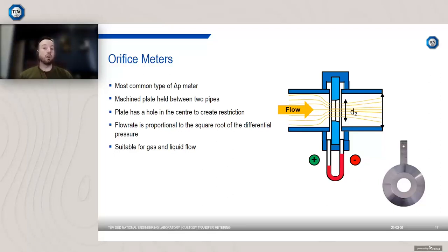So orifice meters are extremely common. They're actually the most common type of differential pressure meter. It's estimated that around 40% of industrial flow meters are differential pressure meters, and a large majority of those are orifice plates. So how does an orifice plate work? Well, it's quite a simple thing. It's a machined plate held between 2 pipes. The plate has a hole in the center that creates a restriction in the flow. As the flow goes through the restriction, the velocity increases, and as a result, the static pressure drops. By measuring that differential pressure, you can determine the flow rate, because the flow rate is proportional to the square root of the differential pressure.